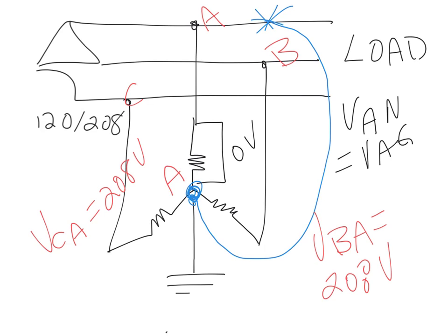So by applying line voltage across those two phases, here's what's going to happen to your bulbs: your bulbs are normally seeing 120 volts, which means they're bright normally. What we've done is we've made them a whole lot brighter because we've applied more voltage across phases. What was C to ground is now C to A, and across B to ground, or B to neutral which is now B to A, those two lights are going to be bright. Meanwhile, phase A to ground or A to neutral is going to be zero volts because it's now the same point, which means that lamp will be out.